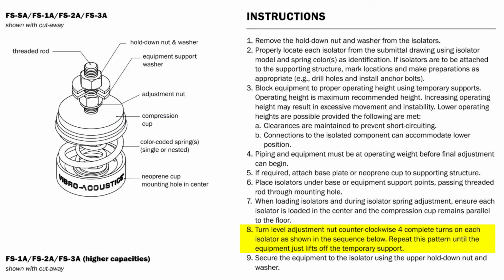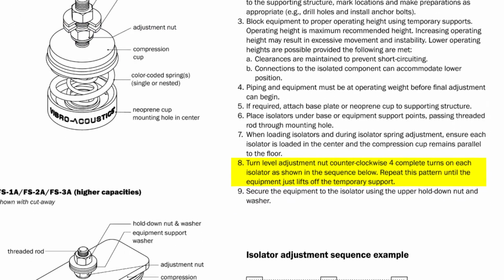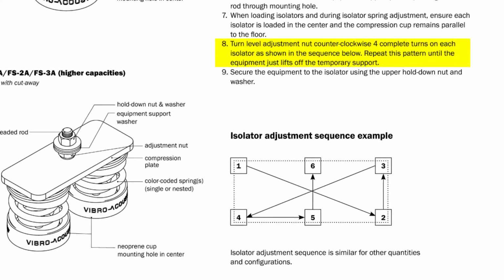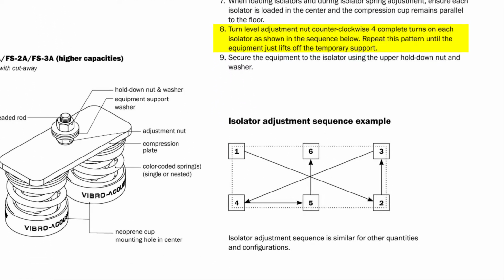Here it says to adjust the isolator, the adjustment nut, which is welded to the threaded rod, should be turned 4 complete turns before going to the next isolator, following the adjustment sequence as shown in the diagram below. This sequence diagram shows 6 isolators, which is more common on a larger inertia base and equipment, but these inertia bases only have 4 isolators, so it's even easier.